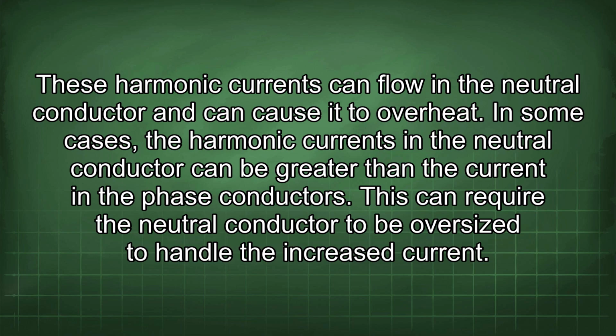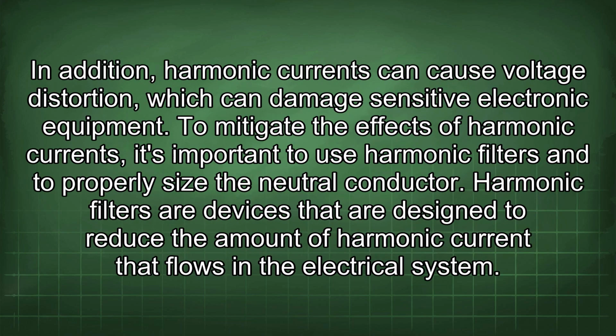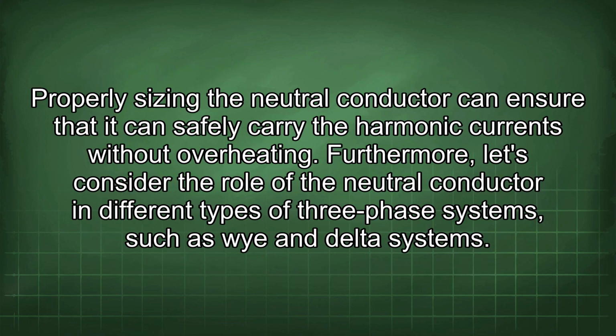In some cases, the harmonic currents in the neutral conductor can be greater than the current in the phase conductors. This can require the neutral conductor to be oversized to handle the increased current. In addition, harmonic currents can cause voltage distortion, which can damage sensitive electronic equipment. To mitigate the effects of harmonic currents, it's important to use harmonic filters and to properly size the neutral conductor. Harmonic filters are devices that are designed to reduce the amount of harmonic current that flows in the electrical system. Properly sizing the neutral conductor can ensure that it can safely carry the harmonic currents without overheating.